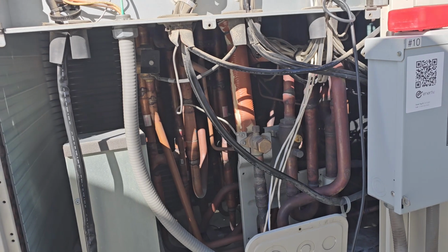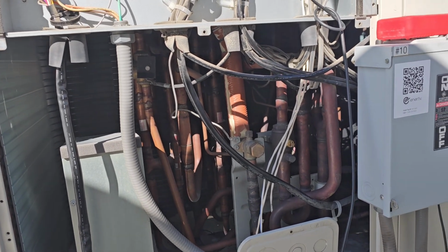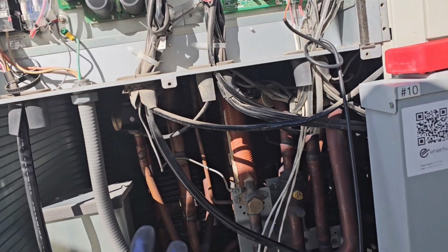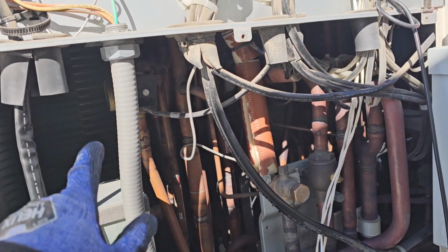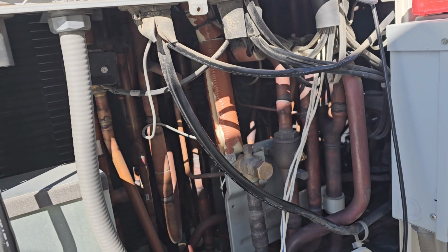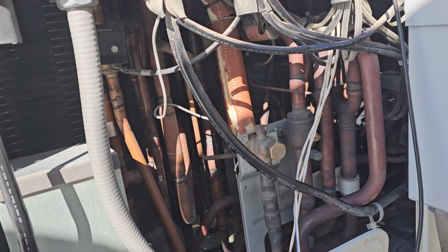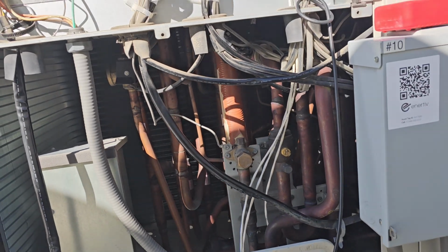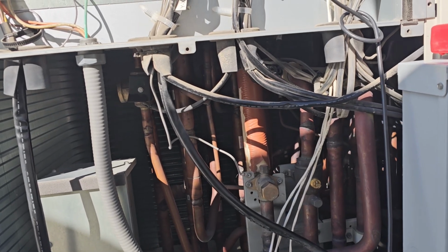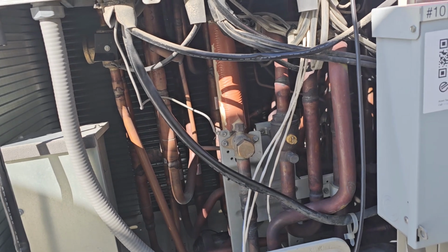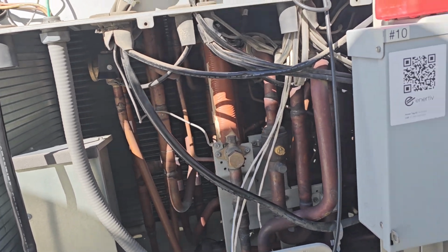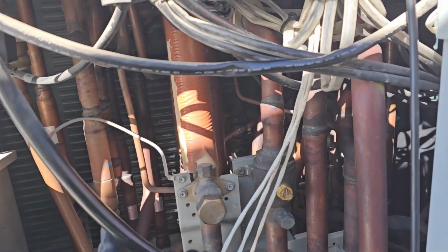Okay, I have refrigerant that doesn't feel like it's flowing very well. I have verified that the four-way valves are switching. I have verified that refrigerant is just not flowing where it should. And think to yourself, okay, so if I really commit to that, what would cause that? Well, I guess ball valves would cause that. They're probably wide open, but I'll just check anyway. And lo and behold, they're closed.